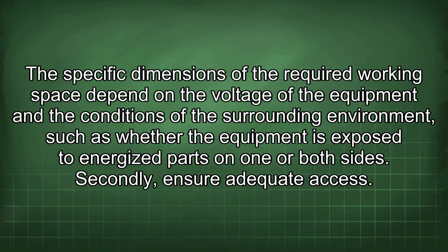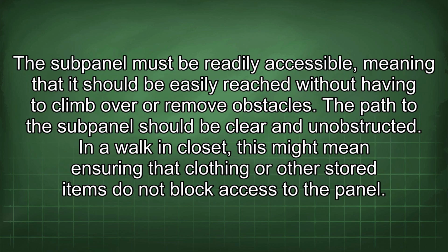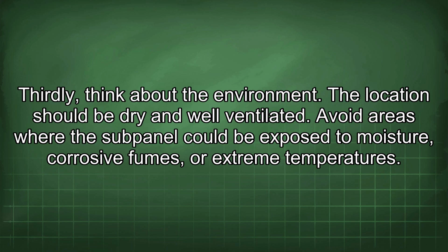Secondly, ensure adequate access. The subpanel must be readily accessible, meaning that it should be easily reached without having to climb over or remove obstacles. The path to the subpanel should be clear and unobstructed. In a walk-in closet, this might mean ensuring that clothing or other stored items do not block access to the panel.